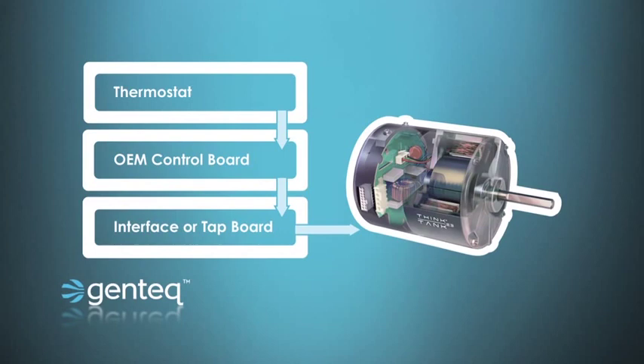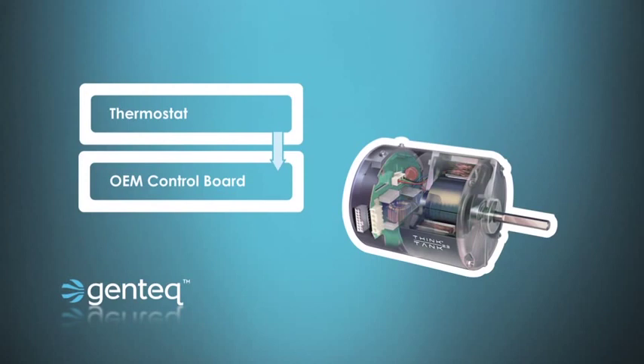At first glance, variable speed looks very complicated, but as you can see it's actually very easy — and as easy as it is, it makes the system do things that no other motor can do. Now let's look at where those controls are located in the HVAC system. Some manufacturers still use a separate board for the communication that goes to the motor: a thermostat sends the demand call to an OEM circuit board, which sends it down to an interface or tap board where you select your airflow settings, and that board sends the proper communication to the motor.